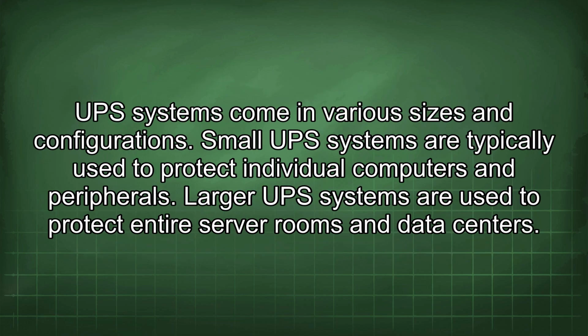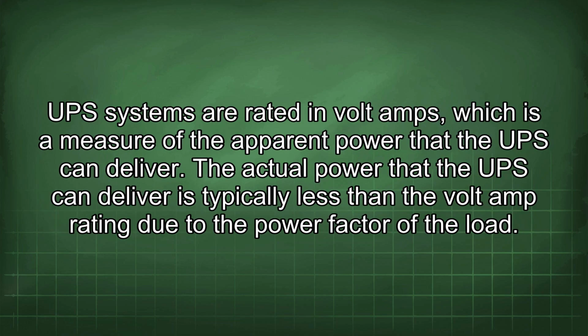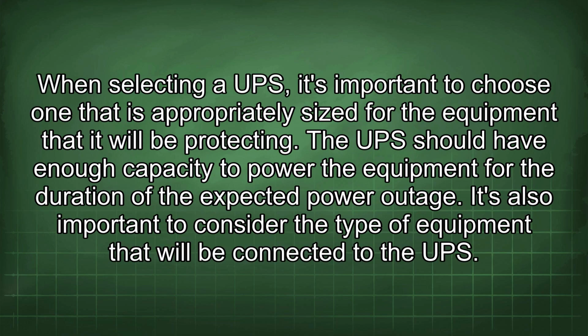UPS systems come in various sizes and configurations. Small UPS systems are typically used to protect individual computers and peripherals. Larger UPS systems are used to protect entire server rooms and data centers. UPS systems are rated in volt amps, which is a measure of the apparent power that the UPS can deliver. The actual power that the UPS can deliver is typically less than the volt amp rating due to the power factor of the load. When selecting a UPS, it's important to choose one that is appropriately sized for the equipment that it will be protecting.